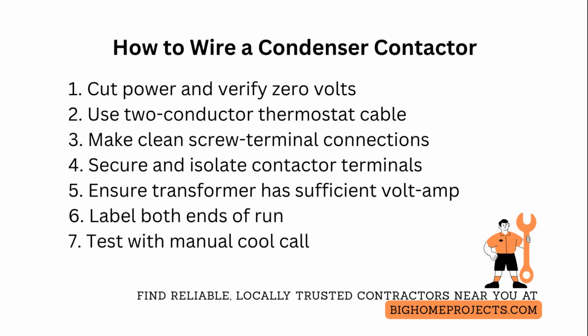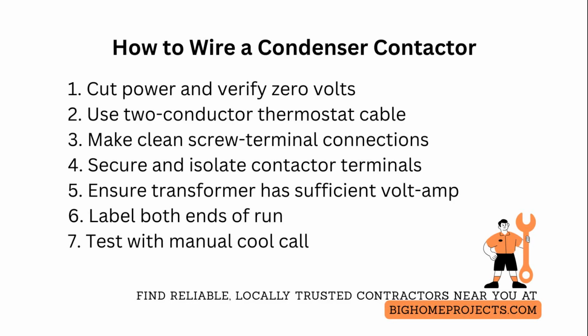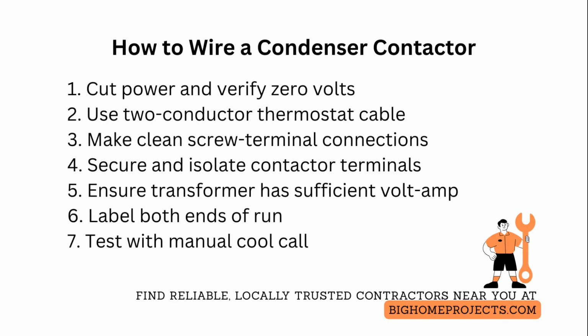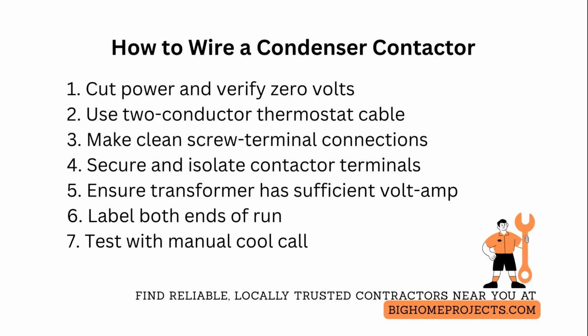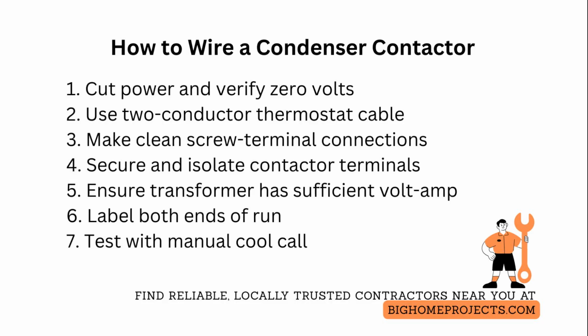Secure with ring terminals or properly crimped spade lugs and isolate with dielectric grease to slow corrosion. If the system has a fused outdoor leg or a high pressure cutout, wire the contactor coil in series with those safety devices as specified by the manufacturer so the compressor cannot start if a safety opens.